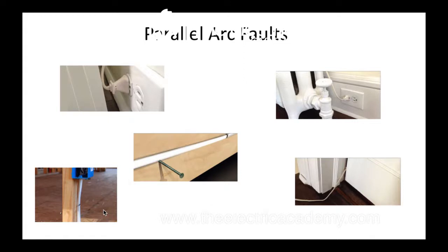You've got to be careful because these parallel arc faults are super dangerous — it might not cause enough current for the breaker to trip, but that arc, with the voltage present, is pushing current across and it can get super, super hot. They say that some arc faults can get up to 9,000 to 10,000 degrees Fahrenheit. That's where you're getting your fires from. It's very important that we understand the difference between a series arc fault and a parallel arc fault. Parallel arc faults are very dangerous; series arc faults are dangerous but not as dangerous as a parallel.